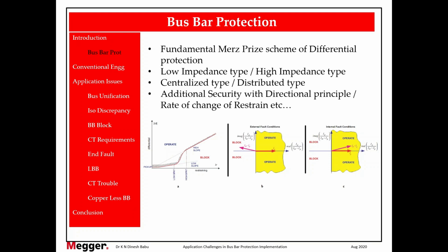So the relay also checks both. Differential and restraint both increased, trip. Only differential increased, restraint is not increasing, don't trip. So whatever I am discussing is actually not a sophisticated new algorithm. It's all already inbuilt in the numerical relay.